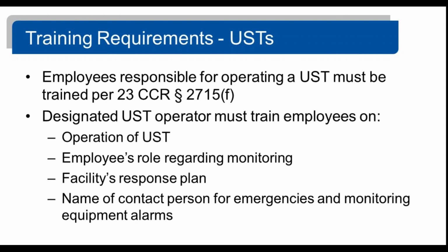So there is a specific certification for those who are providing training for employees who operate a UST system. So the training specifically has to be provided by a UST designated operator, typically referred to as a DO. And the employees must be trained on proper operation of the underground storage tank, their specific role regarding monitoring of that UST system.